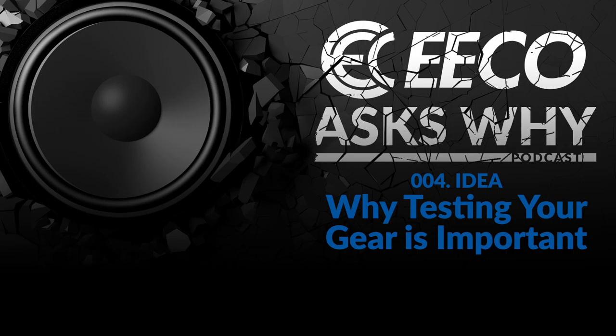That's kind of the gear. Okay, when we start talking about the breakers and making sure that the breakers are going to operate properly, we can actually do that through two different methods. One is called primary injection or current injection testing, and the other is called secondary injection testing. When you have an electronic trip unit in the breaker, we can perform what's called secondary injection, where we plug a test set into the trip unit itself, and we run the trip unit through all of its trip functions, okay?